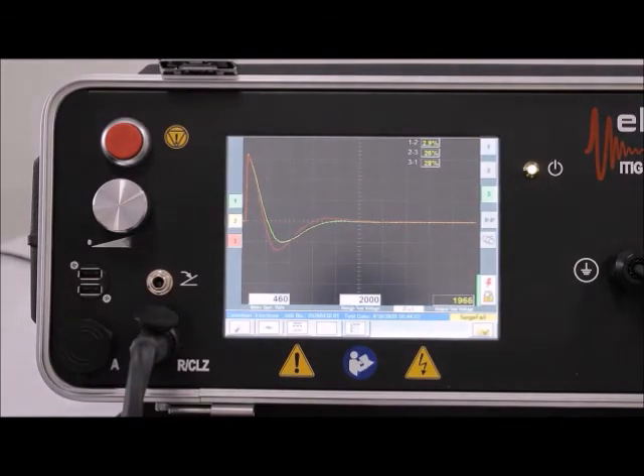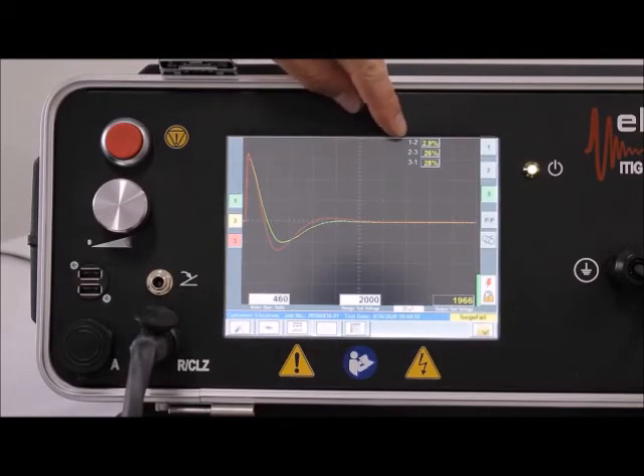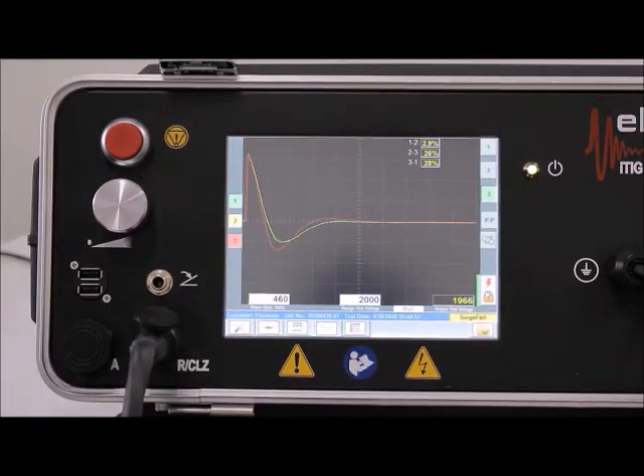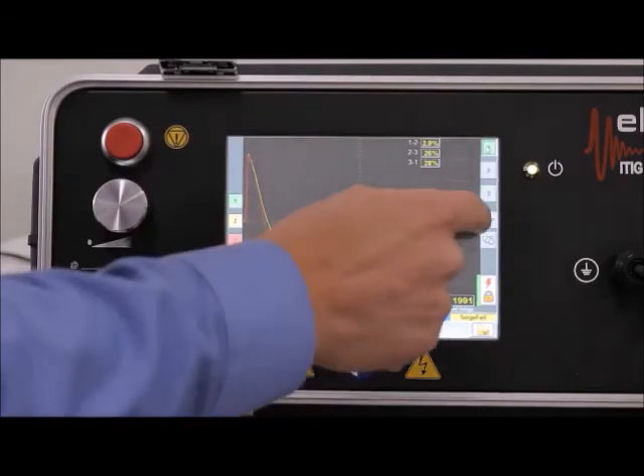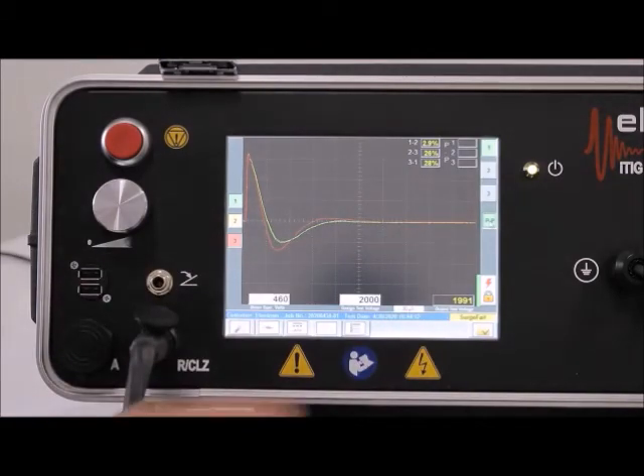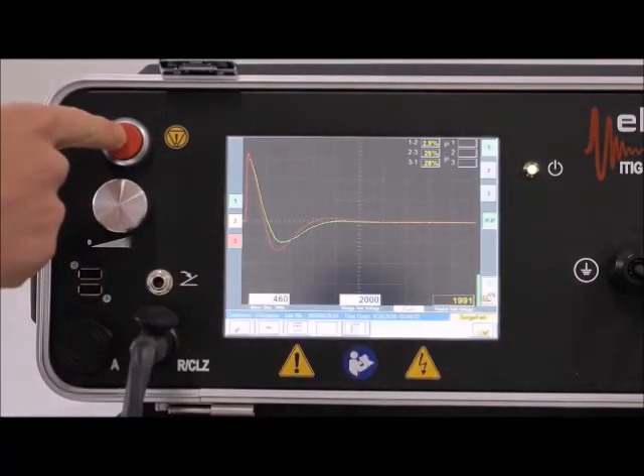And now we have our surge comparison. As you can see, we have a surge fail. The percentages are greater than our default pass-fail of 10%. The reason for this is that we have an assembled motor, and the orientation of the rotor is influencing our surge waveforms. So what we're going to do is redo the test starting with phase 1, but now we're going to select the pulse-to-pulse feature. Arm the instrument, press the red button.